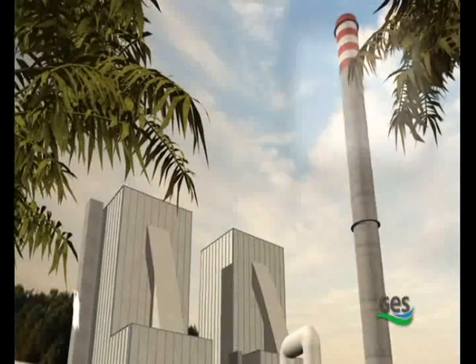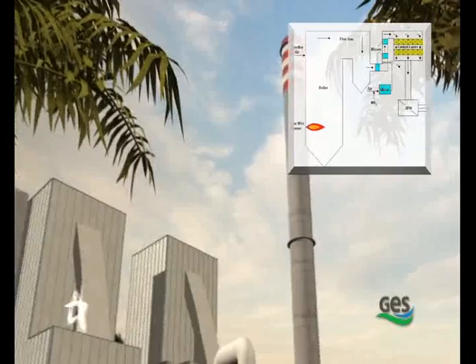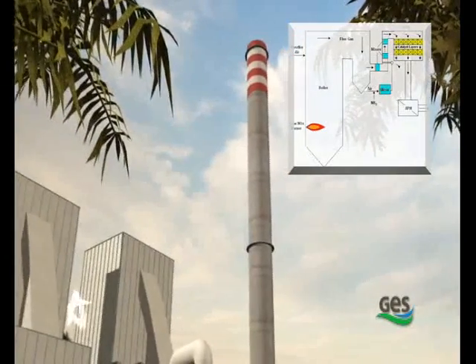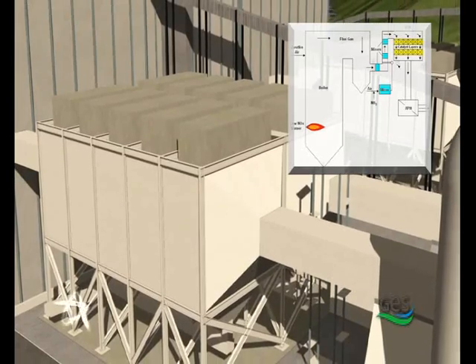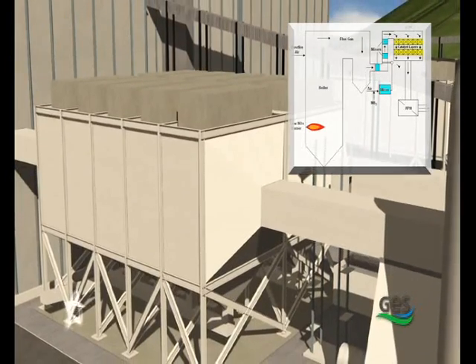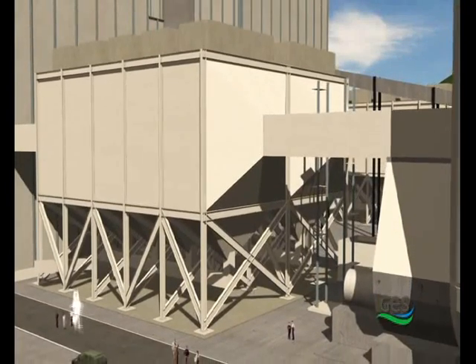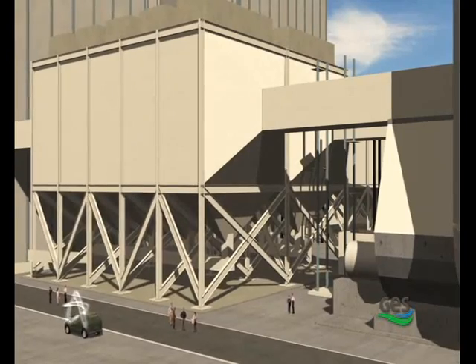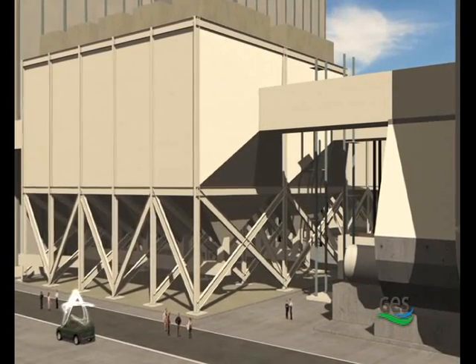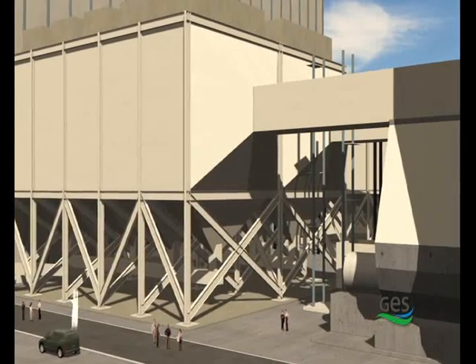The plant is equipped with continuously working flue gas cleaning system comprising denitrification, desulfurization and dedusting units. Regarding denitrification system, the latest technology introduced to Turkey recently will be utilized. That is, NOx content of the flue gas is reduced by 3 consecutive stages. The low NOx burners, overfire air and selective catalytic reduction process on the path of the flue gas before the air preheater.